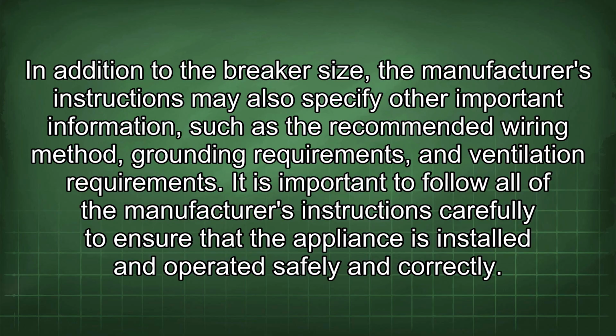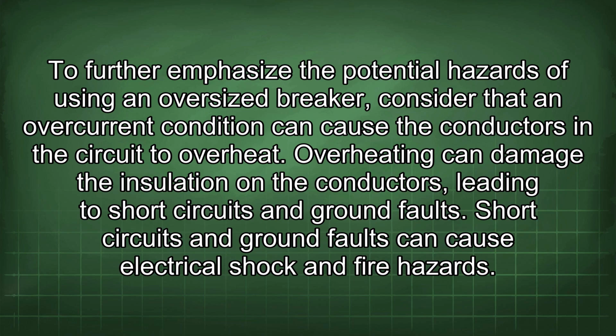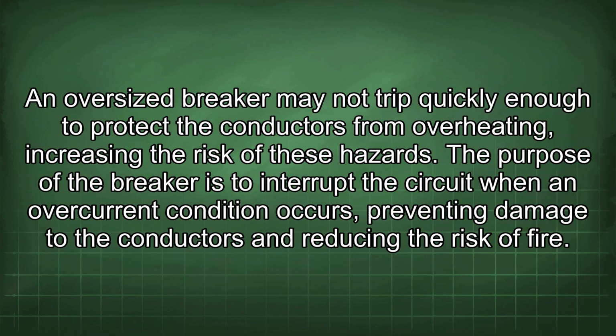To further emphasize the potential hazards of using an oversized breaker, consider that an overcurrent condition can cause the conductors in the circuit to overheat. Overheating can damage the insulation on the conductors, leading to short circuits and ground faults. Short circuits and ground faults can cause electrical shock and fire hazards. An oversized breaker may not trip quickly enough to protect the conductors from overheating, increasing the risk of these hazards.